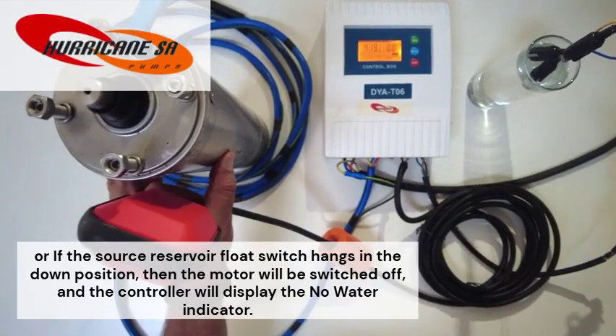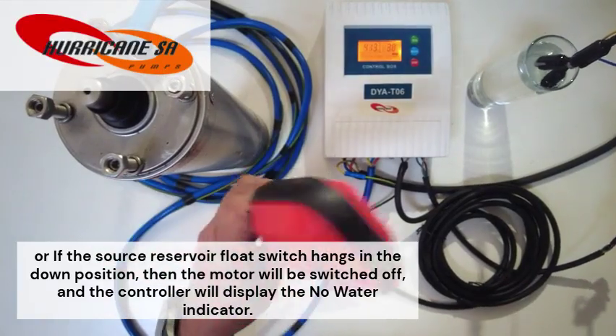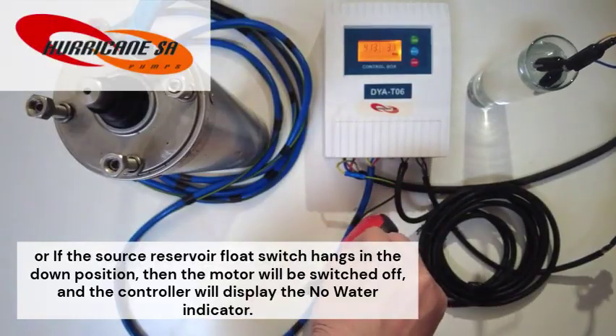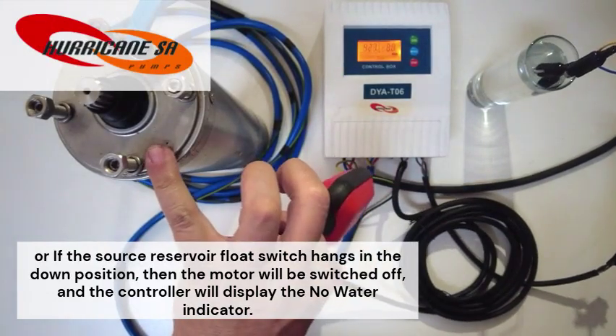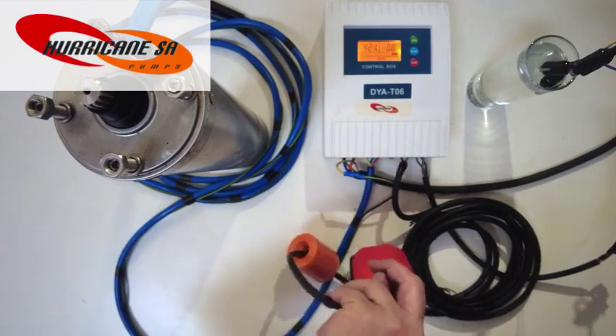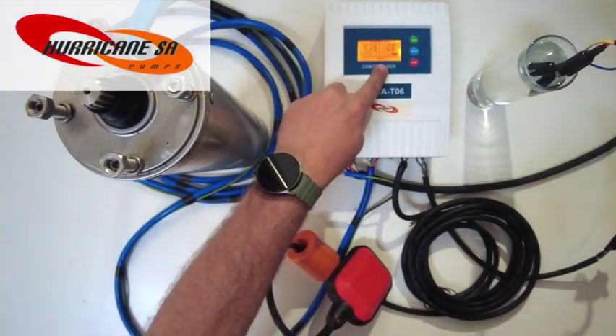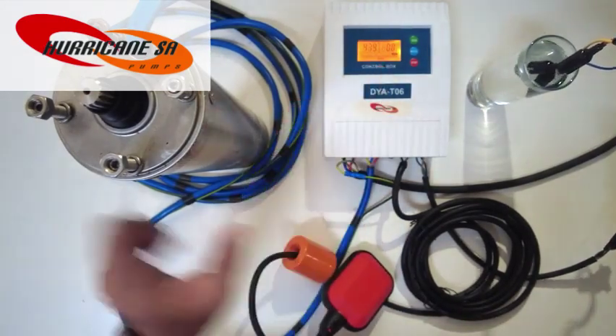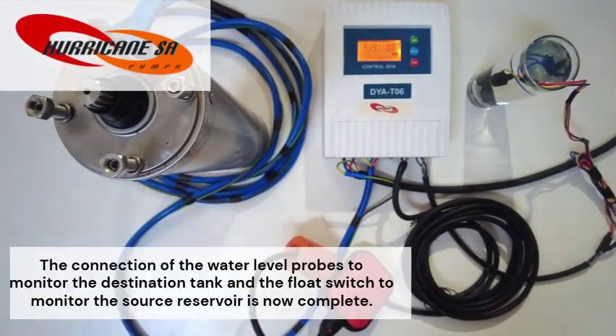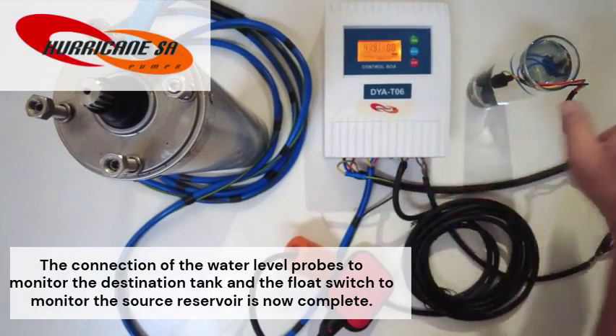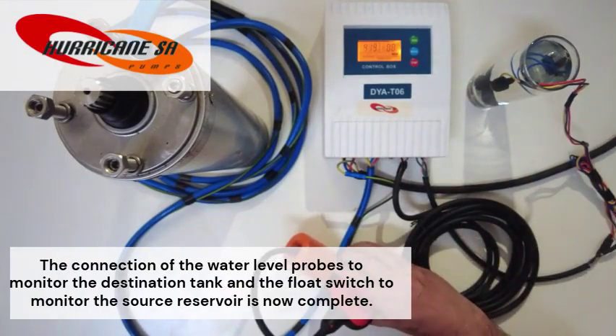Or if the source reservoir float switch hangs in the down position, then the motor will be switched off and the controller will display the no water indicator. The connection of the water level probes to monitor the destination tank and the float switch to monitor the source reservoir is now complete.